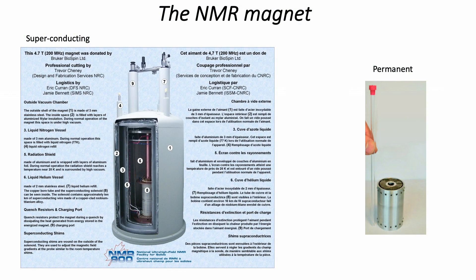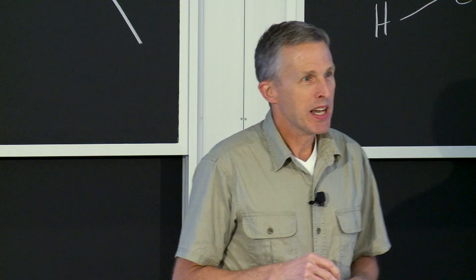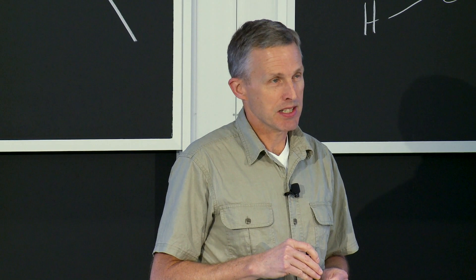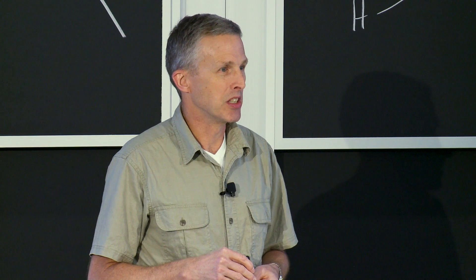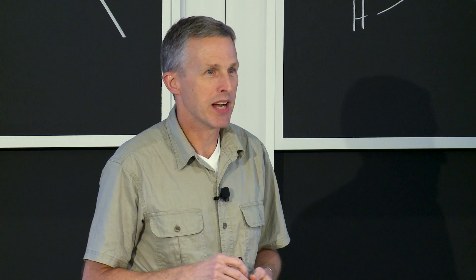You've got to have a strong magnetic field to immerse your sample in, supplied by a strong magnet. Magnets come in two flavors. In the benchtop instruments they are a permanent magnet — made from a neodymium iron boron alloy, the same type used in hard drive magnets. There's been great improvement in those over the past 15 years or so. It used to be difficult to engineer permanent magnets with a uniform magnetic field, but they've been able to do that, and so there are a lot of benchtop instruments out there now.